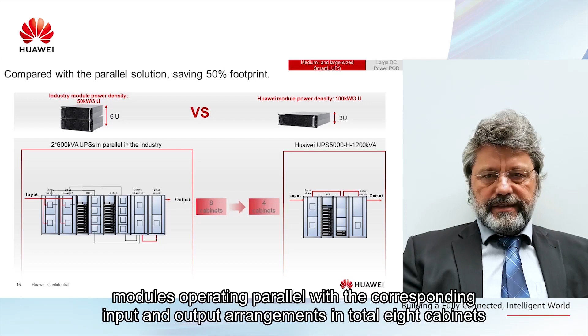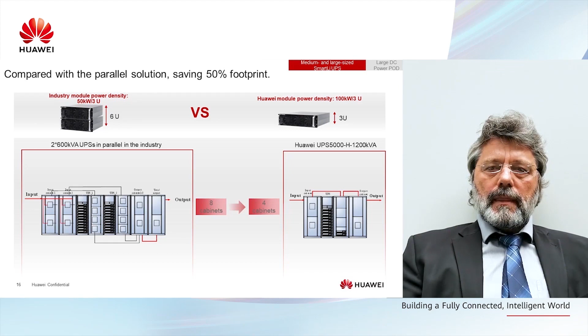How does the outstanding power density perform in terms of footprint? On this slide you can see the front view of 2 UPS systems with a total power of 1200 kVA. On the left side you see the combination of 2 600 kVA UPSs based on 50 kW modules operating in parallel with the corresponding input and output arrangements, in total 8 cabinets. On the right side you see the Huawei Fusion Power 1.2 MW containing the 3U 100 kW power module with in total 4 cabinets. This is a saving of 50%.